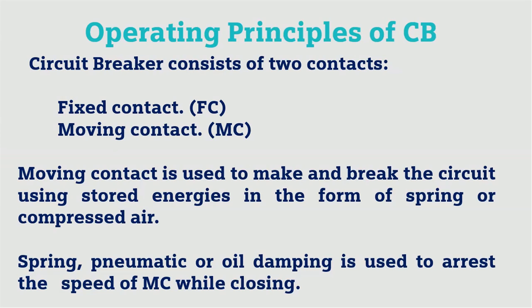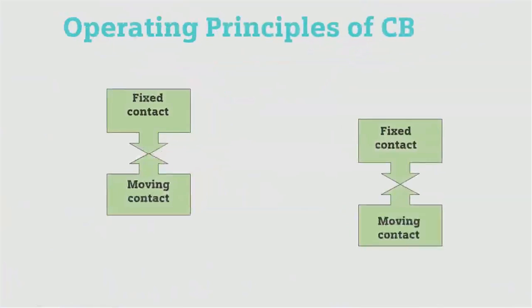The circuit breaker consists of two contacts: fixed contacts and moving contacts. The moving contact is used to make and break the circuit using stored energy in the form of a spring or compressed air. A spring, pneumatic, or oil damping mechanism is used to control the speed of the moving contact while closing.